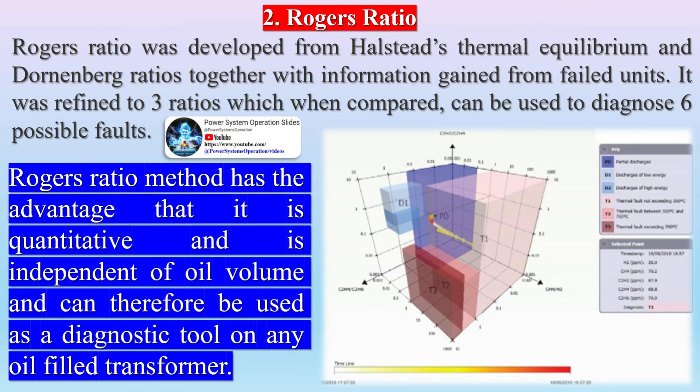The six main fault zones are represented along with a DT zone indicating a thermal and electrical fault. The fault zones have been determined based upon a large sample of faulty transformer cases which have subsequently been inspected visually. This is a useful technique but is limited to detecting fault conditions when they have already formed, allowing a progression of an issue to be followed.